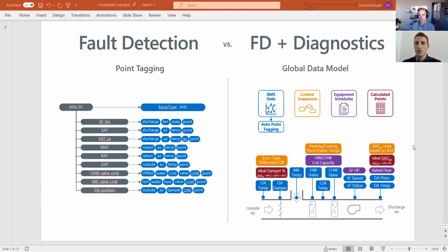You need to give each of those points a meaning, and map them to a data model that knows, hey, this point that I'm bringing onto this equipment is actually an air handling unit, and that discharge air temperature is going to be impacted by the reset strategy used in the control sequence. This outside air damper is going to be impacted by the economizer type. To understand those nuances, you have to go beyond what's in the actual BMS controller.